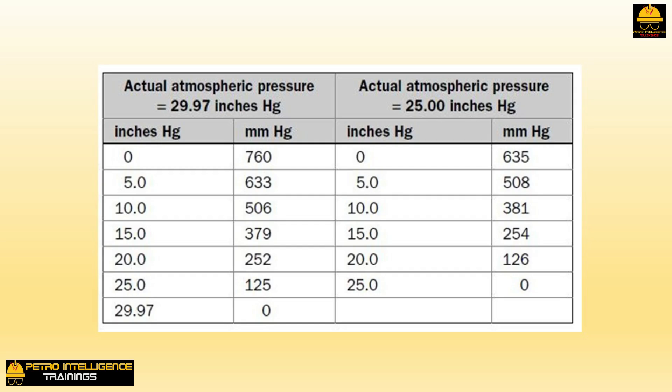To calculate a jet's compression ratio: one, measure the jet's suction pressure and convert to millimeters of mercury; two, measure the jet's discharge pressure and convert to millimeters of mercury; three, divide the discharge by the suction pressure. It is not uncommon to find a proper jet developing an 8-to-1 ratio; more typically jets develop a 3-to-1 or 4-to-1 compression ratio. Any jet with less than a 2-to-1 compression ratio has a serious problem, but not necessarily with the jet itself.